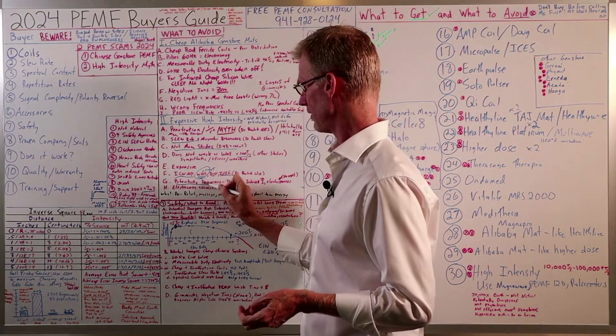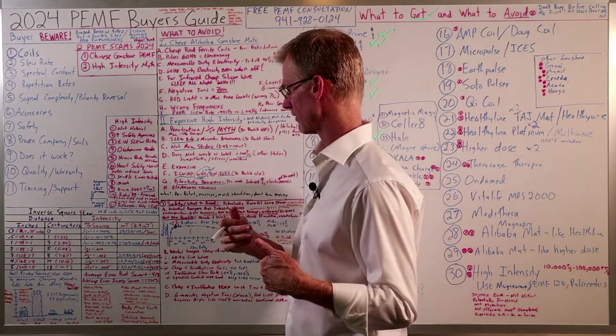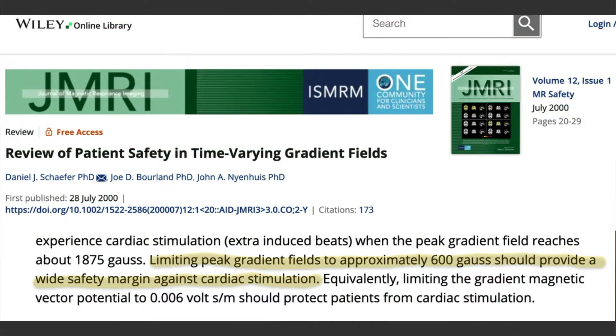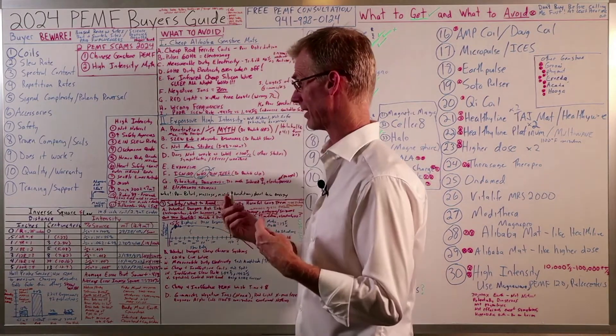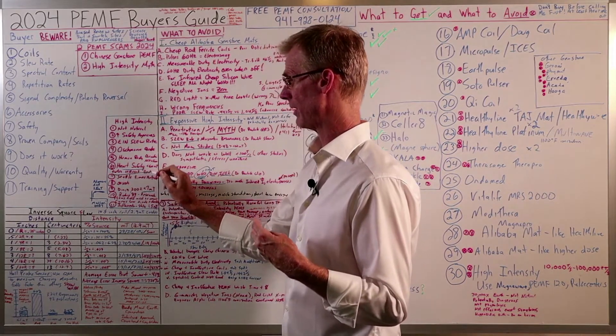These high-intensity fields are potentially dangerous. One study showed that for the heart, you want to stay below 600 Gauss (60 millitesla), or you can induce an extra heartbeat — an unfavorable reaction called extra induced beats — when you go above 60 millitesla.